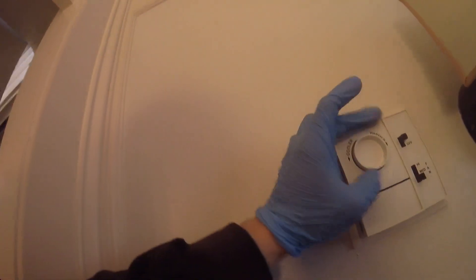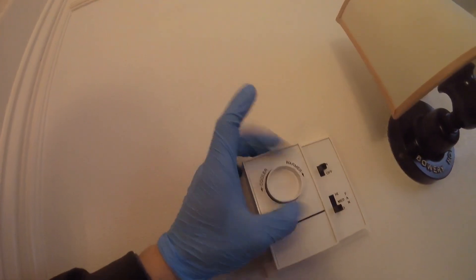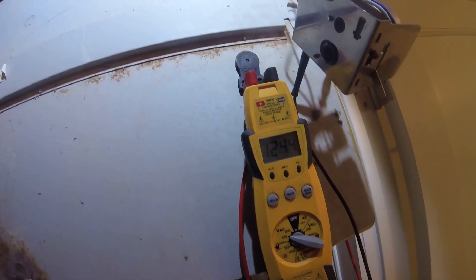I'm going to set it over. The actuator is disconnected. It's hanging on the ceiling there. Very difficult to get the control. Let's see if we get voltage. We've got to figure out what's wrong before I can mount my thermostat and wiring. Alright, we have 120 volts. So we are getting power.